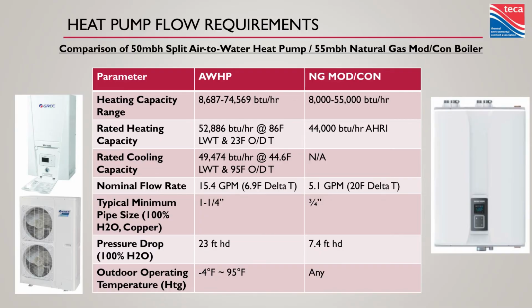Something else to think about. I know it doesn't get above 95 that often, but if you want to do domestic hot water off of your air-to-water heat pump and you live somewhere where that's going to be a problem, you're going to need to plan for some summer domestic hot water. Or if you're doing chilled water cooling with your system, you're going to need to figure out which one's going to take priority in summer, because trust me, people that don't have hot water and don't have air conditioning when they need it are the most irate customer you can deal with.